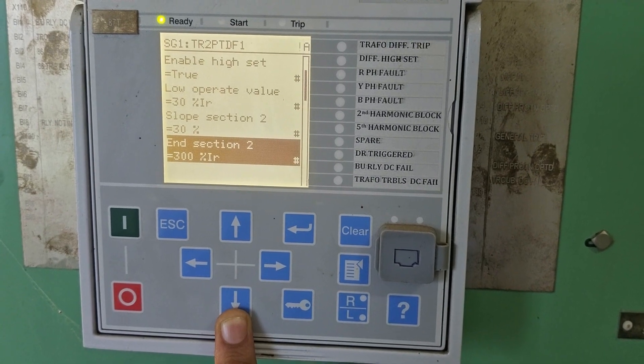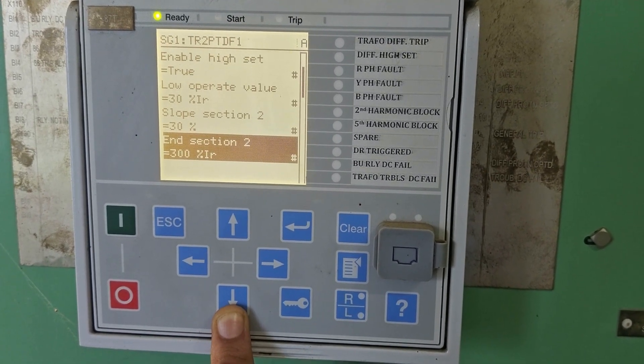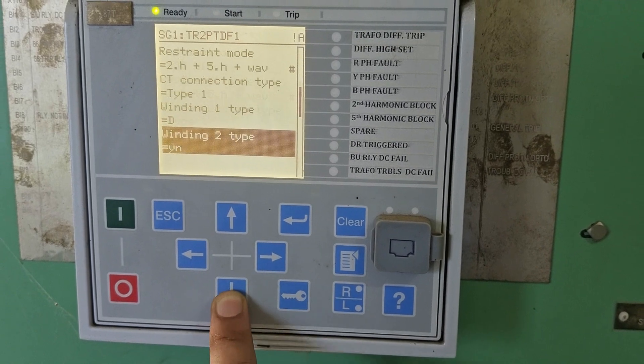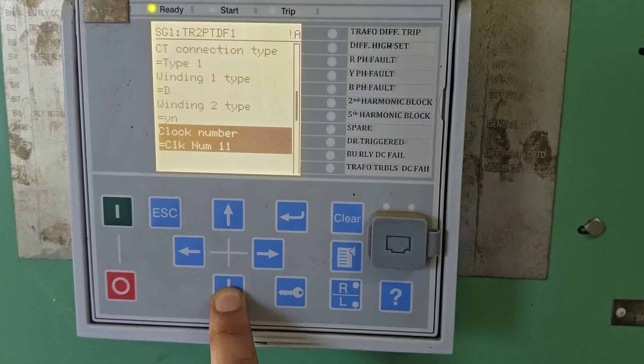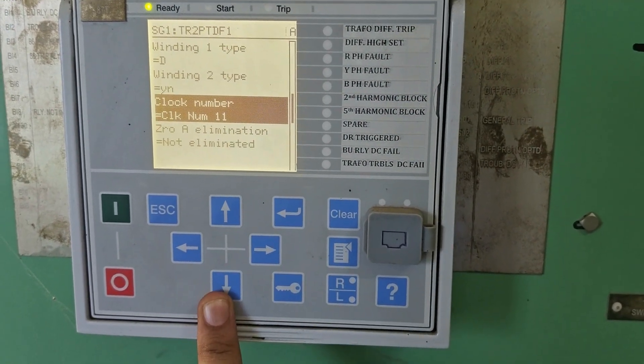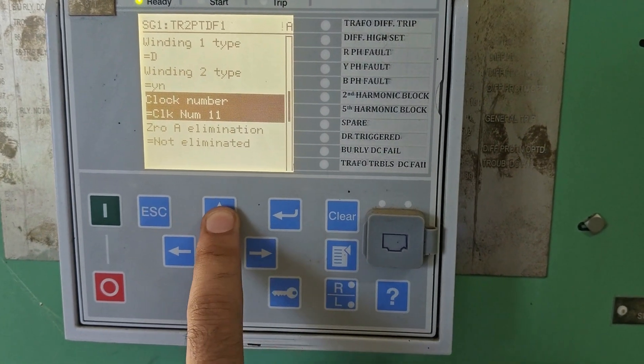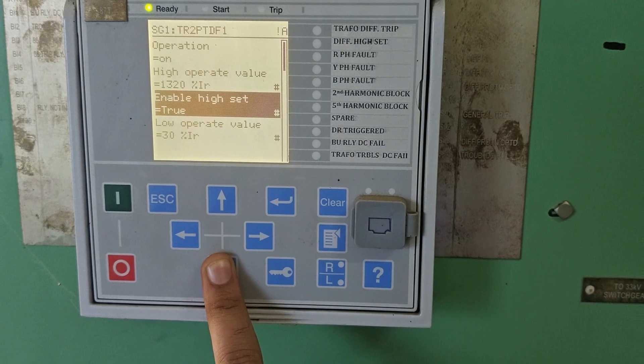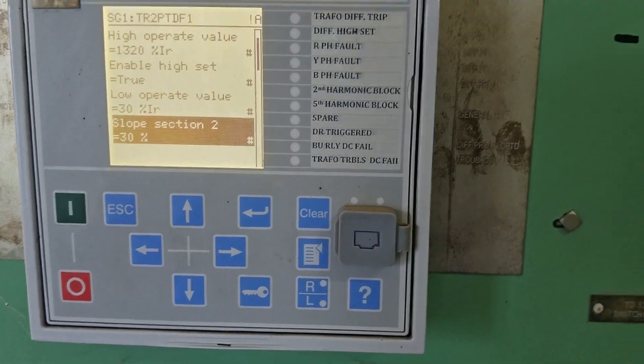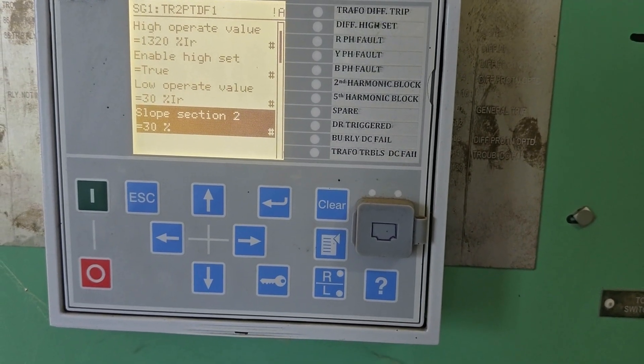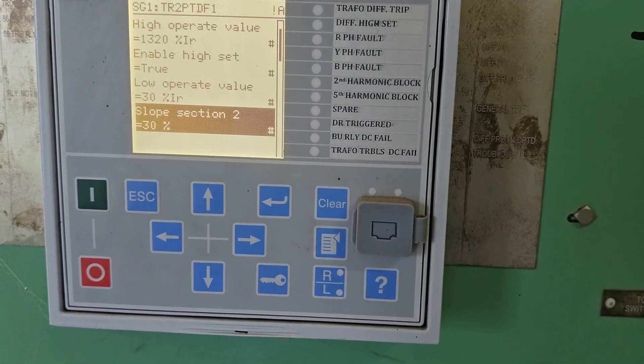The high set enable is TRUE and the low operate value is 30%. So if the differential current exceeds 30%, the transformer will trip, but the fault may be of low intensity. The slope characteristics is essentially a line on the relay's operating characteristic graph; it defines how the relay responds to different levels of differential current.